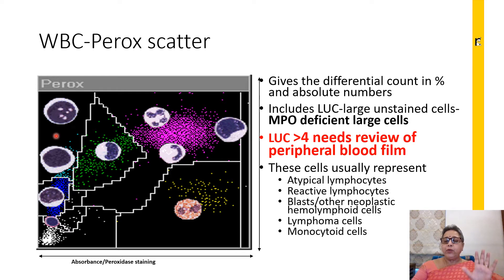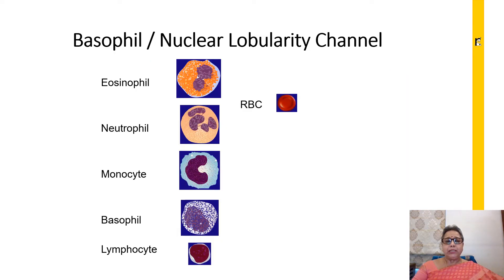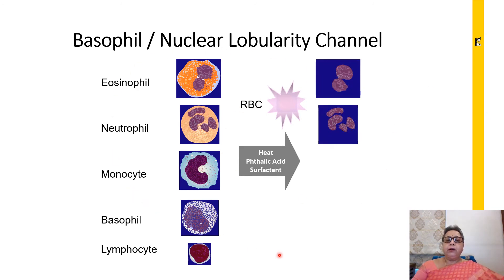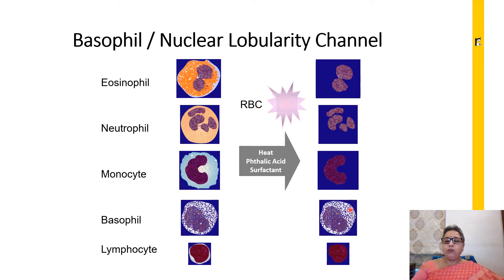This is one scatter obtained after staining with myeloperoxidase. There is a dual method of measuring the WBC — the next method is the basophil nuclear lobularity channel, because in the peroxidase channel, basophils were not yet counted. The basophils are counted in this channel, which primarily measures the total WBC count and the total number of basophils. Here again the RBCs get lysed, and this method makes use of the property that basophils are resistant to stripping by acid.